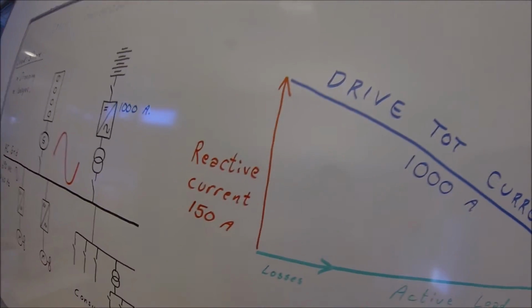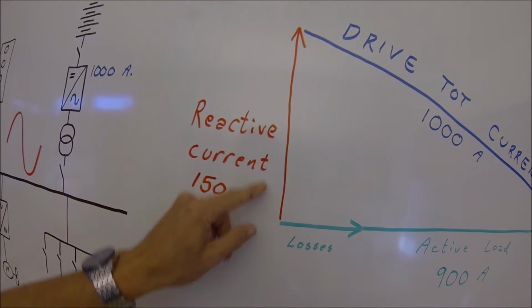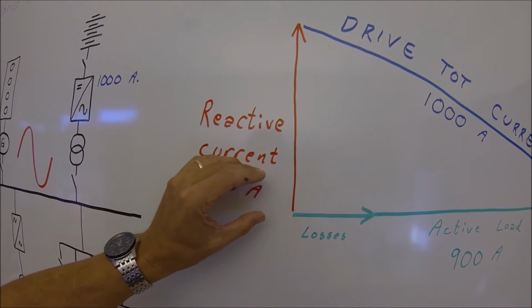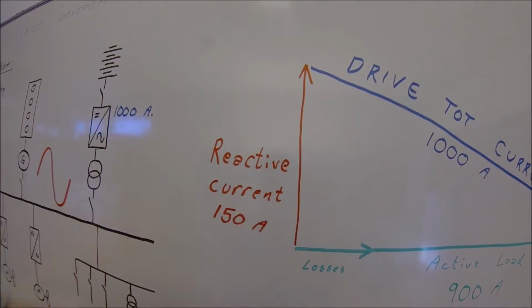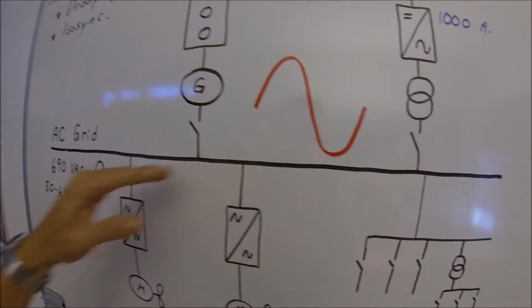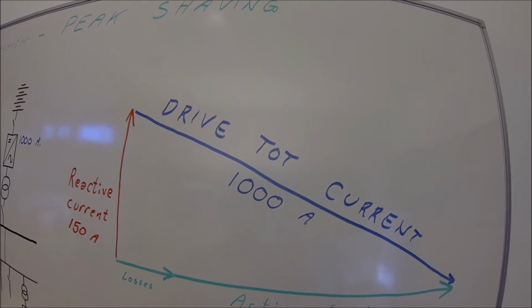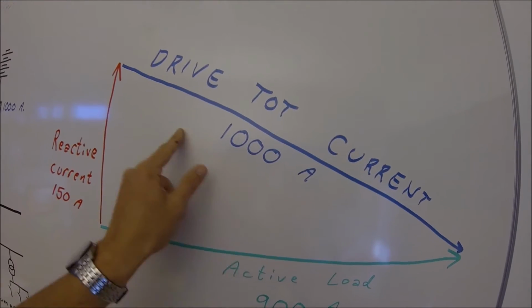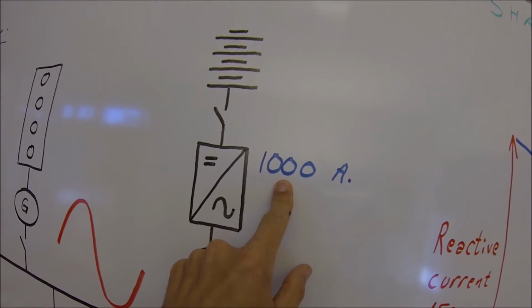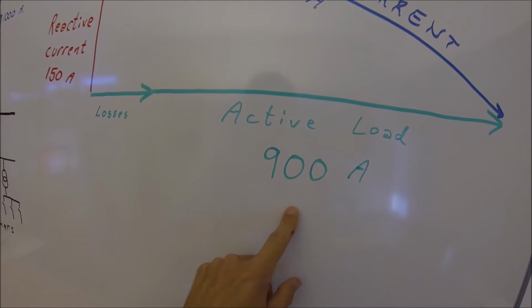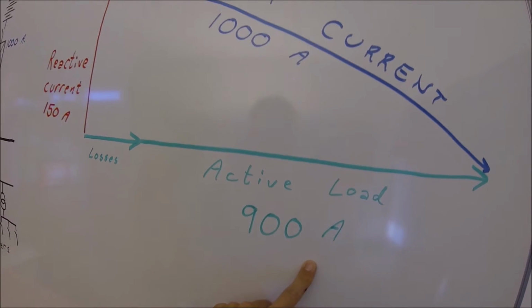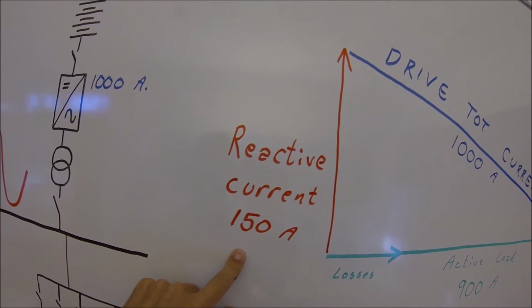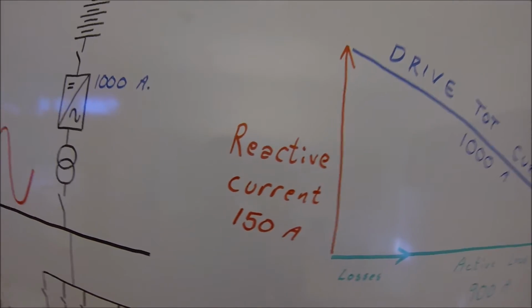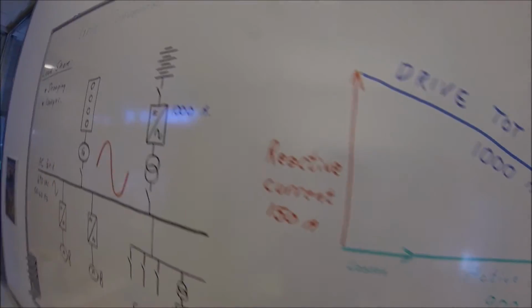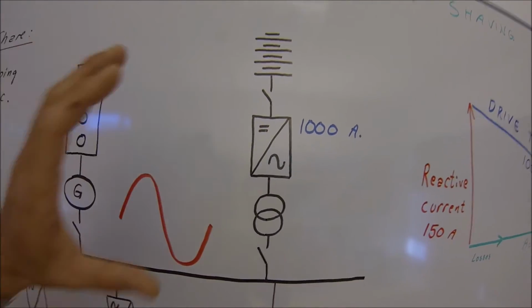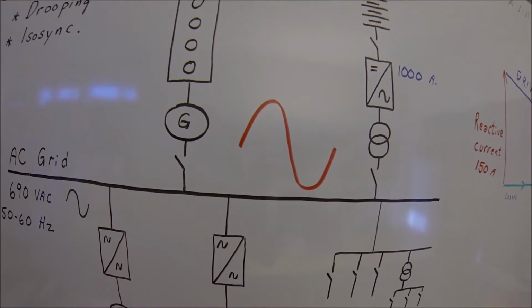However, the drive also has to deal with the reactive current. We can of course minimize it as much as possible, but there is always some kind of reactive current going on to hit the voltage level on the ship grid. The drive total current will be affected by this, because of the total current that we can read here, only about 900 ampere are doing a physical job for us, because we have already occupied some of our drive capacity on handling the reactive current. Be aware of this, because when dimensioning and sizing this system, don't forget that you also have to handle the reactive current in the system.